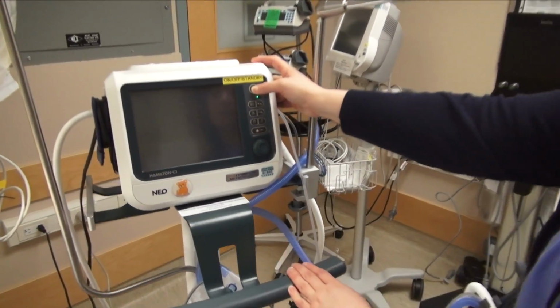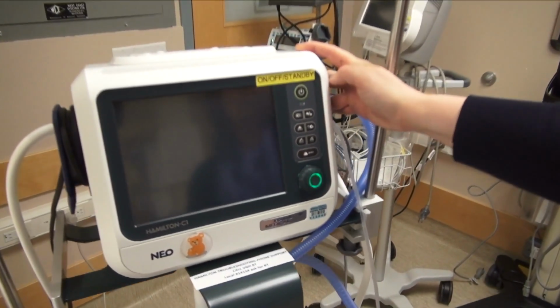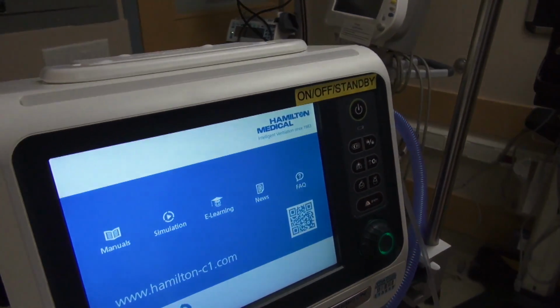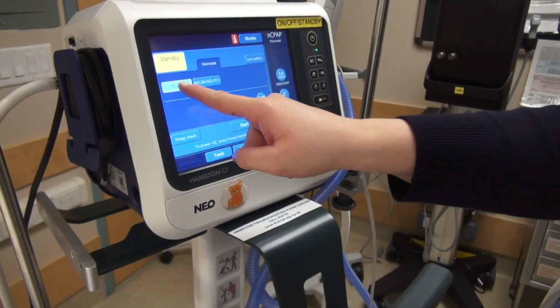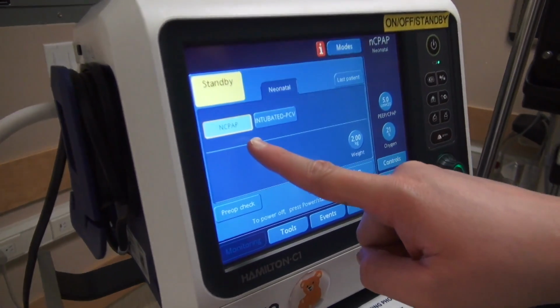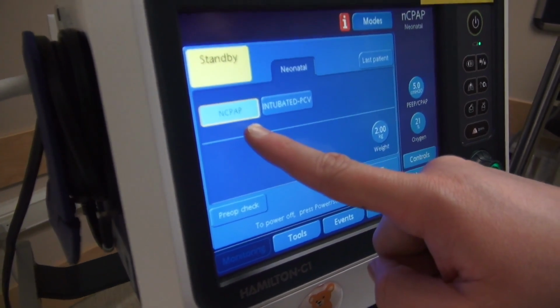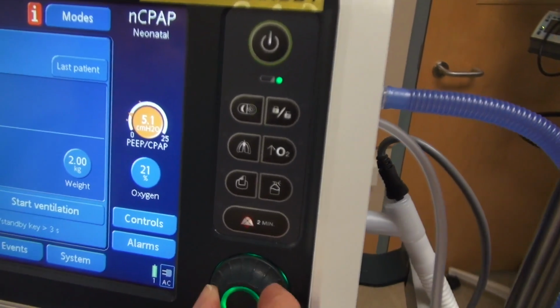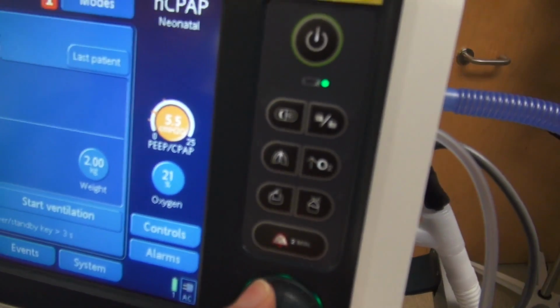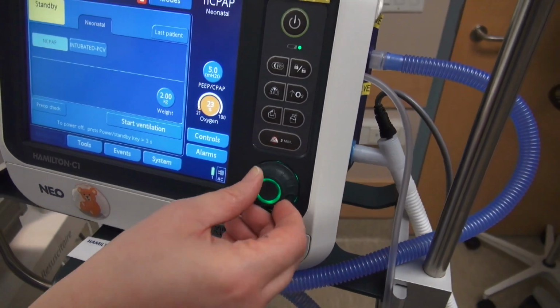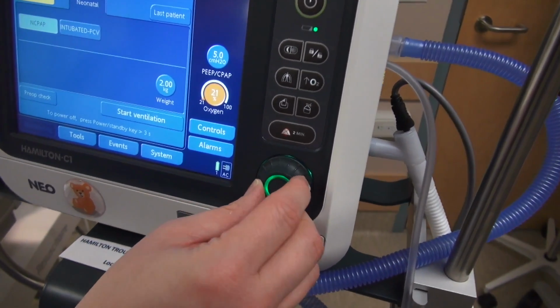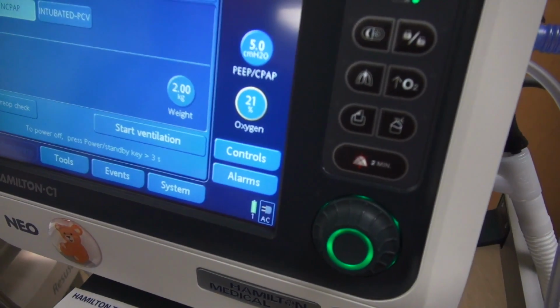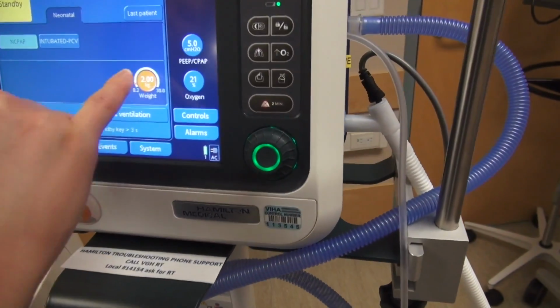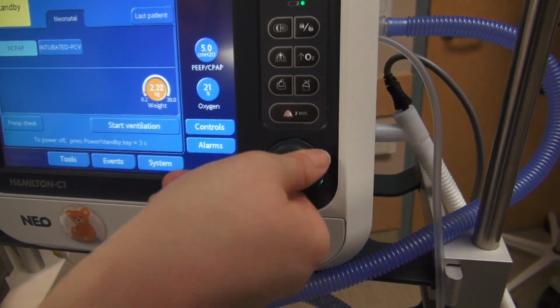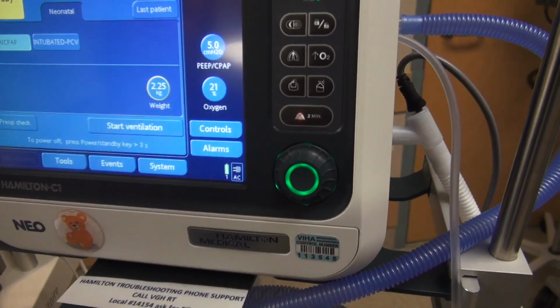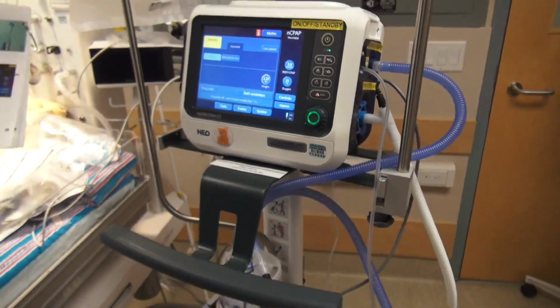Hamilton setup. Step 1. Turn on Hamilton machine. Step 2. Machine will auto default to nasal CPAP mode. PEEP will auto set to 5 of water, and oxygen will auto set to 21% or room air. Confirm settings are accurate. Step 3. Enter weight of the newborn. This is not necessary for nasal CPAP, but it is good practice to get into.